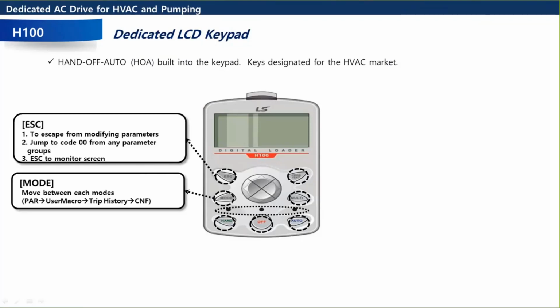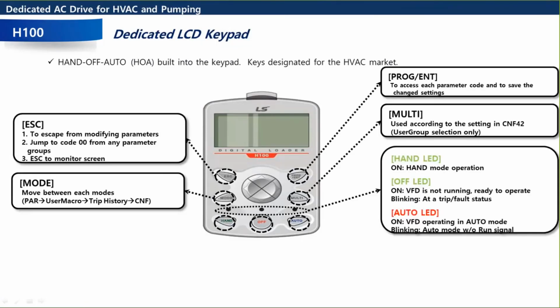So I'm not going to go through all of these, but I'm just going to show you the bottom ones. Here we go. Our Hand Off Auto is on the bottom here. So hand operation is kind of like for testing, or maybe for running when the rest of your system goes down. You press your hand key and you can adjust your speed on the keypad. 30 hertz, 40 hertz, 60 hertz, whatever you want. Okay, so it's kind of like an override. Off, of course, will stop you. It should stop you in hand or in auto. And then auto is typically what's going to be running off of your BAS or your building management system, or however you have your drive set up. It could be a PID loop. It's all fully programmable. So yeah, those three keys are kind of what make this, I guess, the start of what makes this an HVAC drive.